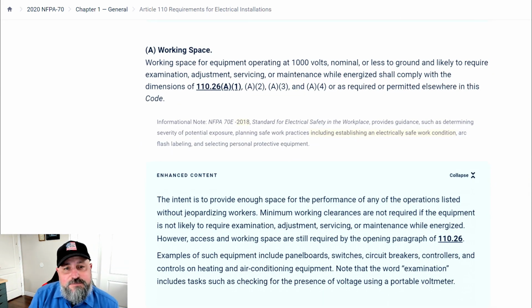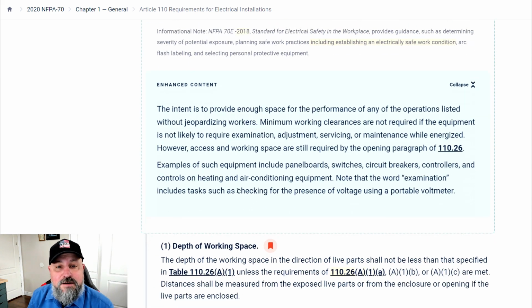A, working space. Working space for equipment operating at 1000 volts nominal or less to ground and likely to require examination, adjustment, servicing, or maintenance while energized shall comply with the dimensions of 110.26(A)(1), (A)(2), (A)(3), and (A)(4), or as required or permitted elsewhere in this code. Let's read this little note here. Information note: NFPA 70E 2018, Standard for Electrical Safety in the Workplace, provides guidance such as determining severity of potential exposure, planning safe work practices, including establishing an electrically safe work condition, arc flash labeling, and selecting personal protective equipment.